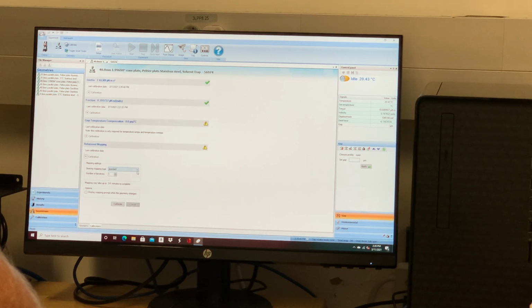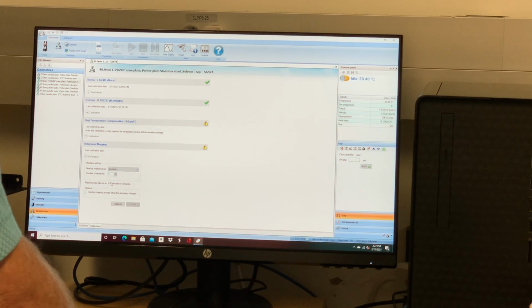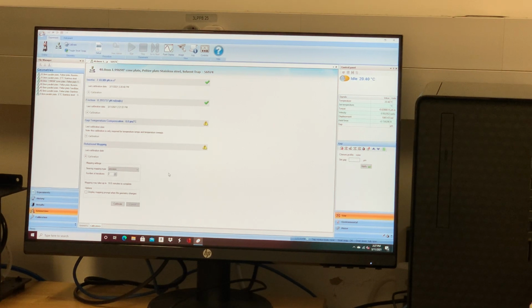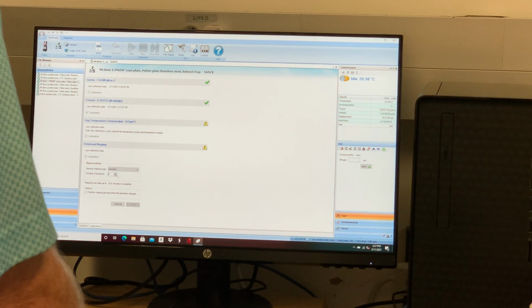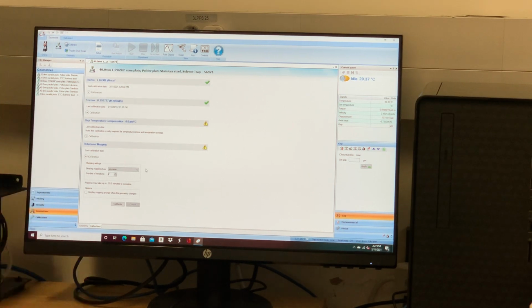There are 3 different levels of mapping: fast, standard, and precision. A lot of it is determined by your sample. If you're running a really low viscosity fluid, water, whatever, at low torque, you're definitely going to need the map. You may need to run a map after every sample. And if you were doing that, you would do a precision map with 2 iterations. That's the most mapping you can do. Anything over that, if you did like 10 iterations, it's not going to do anything. So precision, 2 iterations, and that can take up to 10 minutes to do.